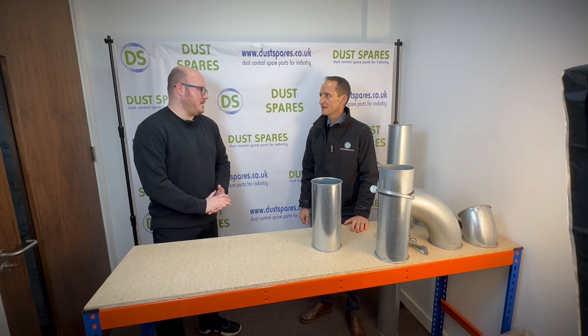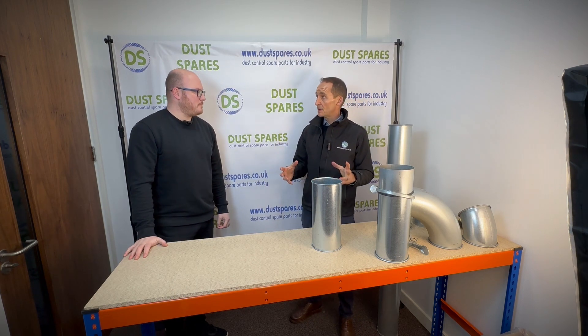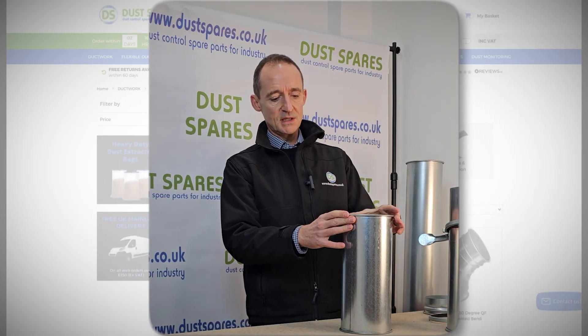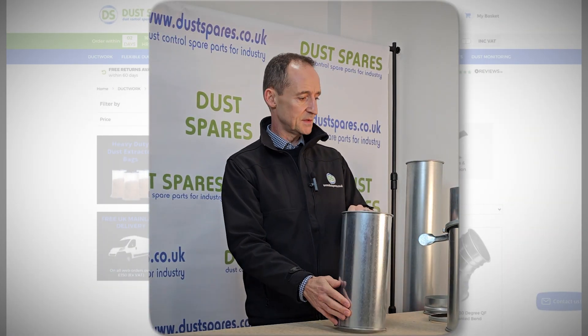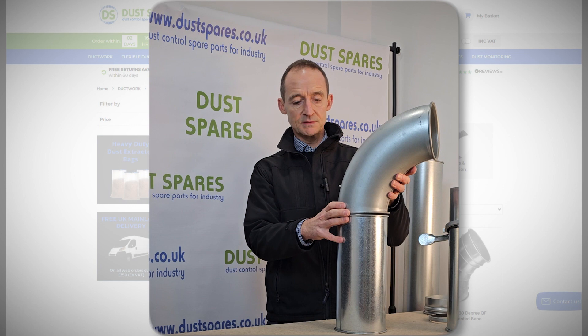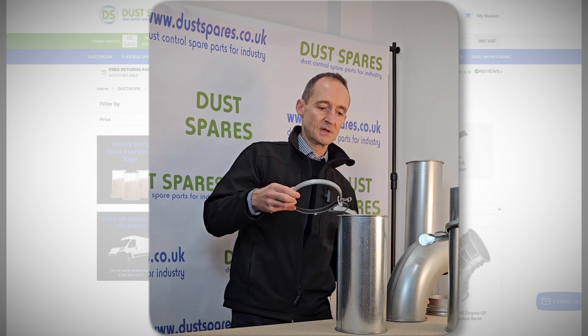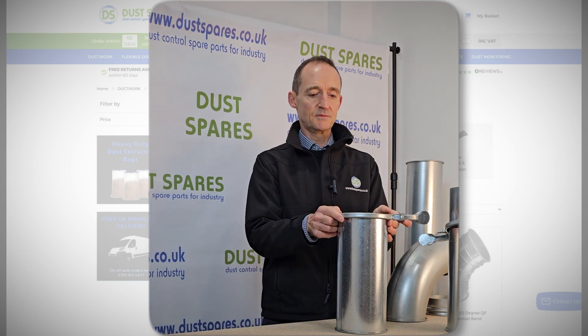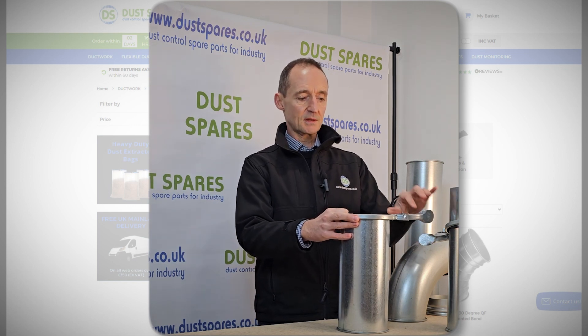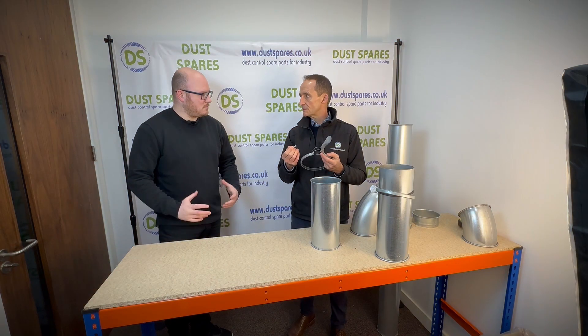How do you connect Nordfab pipes together? With spiral, parts slip in and you use tech screws or rivets, but the Nordfab has a very nice rolled edge on both ends of most pieces, and they can just clip together. If you want to put a bend onto a straight section, you've got two rolled edges, and there's a nice clip which fits over both rolled edges. You clamp it up, click it shut, and then there's a retaining pin to make sure it can't come undone — nice and secure.